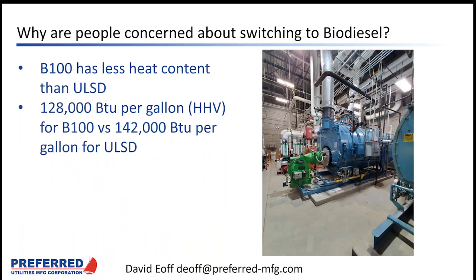Finally, biodiesel has fewer BTUs per gallon than ultra-low sulfur diesel. This means that you're going to burn more gallons of fuel to get the same horsepower out of your boilers or the same kW output out of your gensets. Diesel fuel higher heating value can vary by up to 1% for each truckload. But because of the wide variety of feedstocks that go into biodiesel, the higher heating value range has been shown to be a little wider than with diesel fuel.